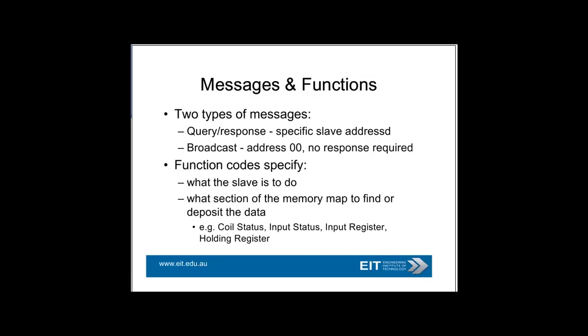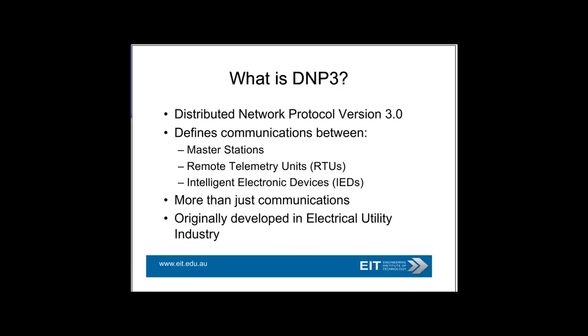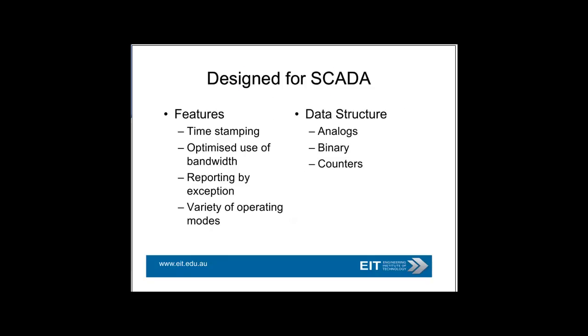DNP3 is a very popular protocol, supposedly to replace Modbus. For wide area networks, DNP3 is very good, while Modbus will probably be more for plants and local systems. DNP3 offers timestamping and reporting by exception, which means reporting when changes occur — Modbus is not very good at handling those sort of issues.